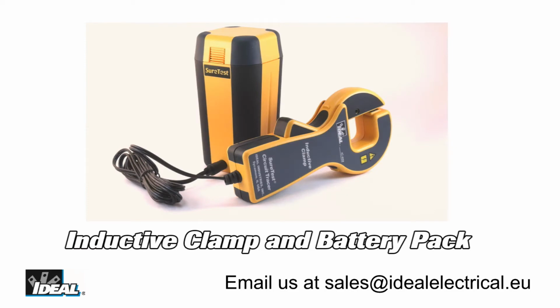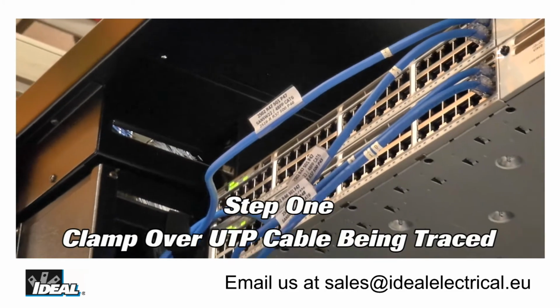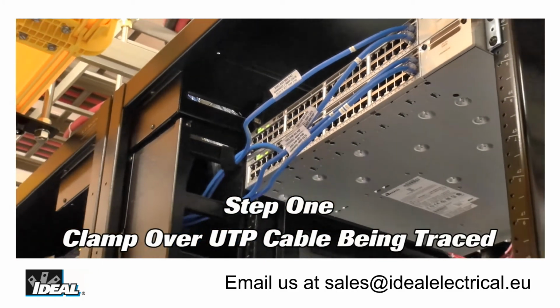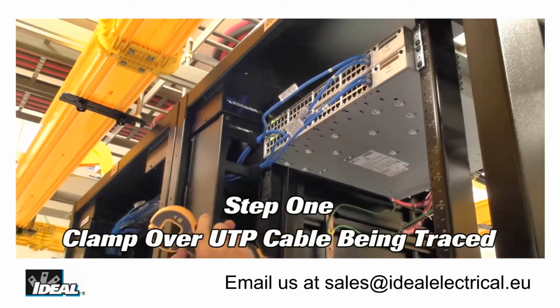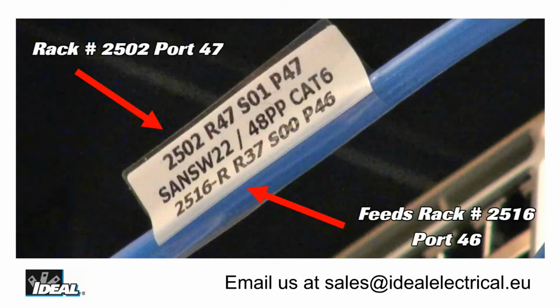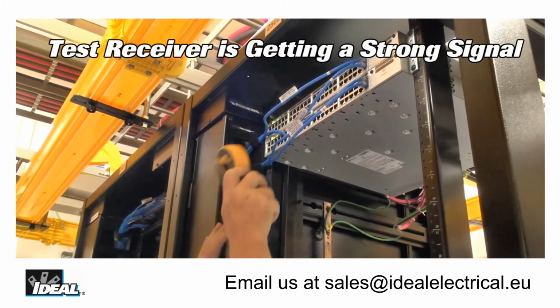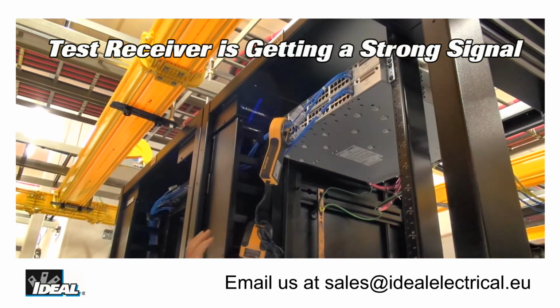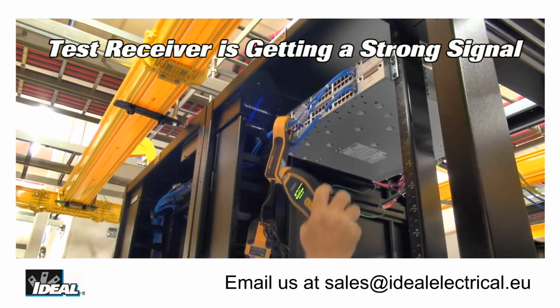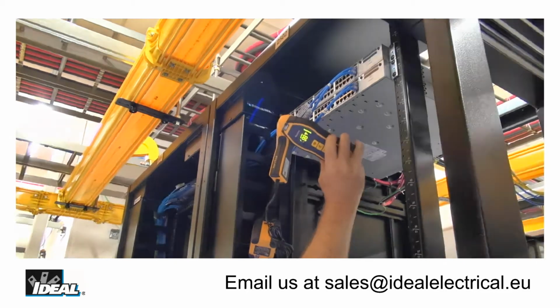Step one is to plug the inductive clamp into the battery pack and clamp it over the cable being traced at the first rack, which is number 2502 in this case. From the label, we know the other end of the cable is in rack number 2516. Using the magnetic strap, hang the battery pack on the rack, then turn on the receiver unit and verify it is getting a strong signal from the transmitter.